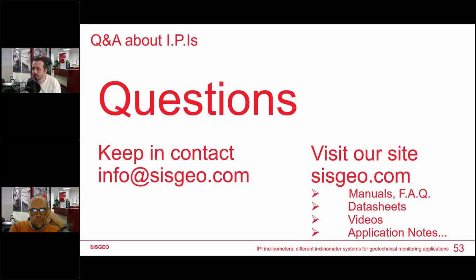How do you initialize and calibrate the in-place inclinometer? If I understand correctly, the question is how to take the reference readings to start. This is described in the ISO standard, but my strong suggestion, as the person who answers this question for Sisgeo every day, is that one of the most important things is to test the probe. I know it sounds like a simple suggestion, but please follow it: test the probe before installation, during installation, and after installation, to confirm it's working perfectly. Then we suggest waiting 24 to 48 hours after installation to let the system stabilize before taking those readings as the reference.